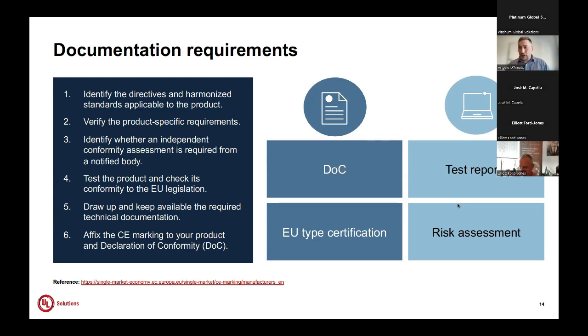In case a harmonized standard is not applied, you need to go to a body like DEKRA or UL to do the EU type examination, called module B. Then, of course, the manufacturer has the responsibility to draw up the technical documentation. This is the point that is lacking now for cybersecurity. And then, of course, they can create their declaration of conformity.